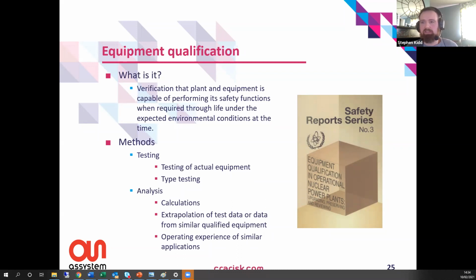We can either do it by testing. We could test the actual equipment itself and demonstrate it's capable of delivering its functions, or we can use type testing, where we test similar equipment or claim qualification based on testing of similar equipment. There's also analysis. We can undertake specific analysis and calculations to provide confidence that the equipment's capable, or we can extrapolate test data or operating experience of similar applications to provide that confidence without actually testing the equipment itself. Or we can do a combination of testing and analysis. Again, it's not a one or the other thing.